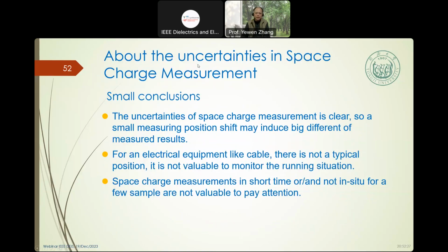So, a small conclusion: the uncertainties of the space charge measurement are clear. A small measurement position shift may induce a big difference in the measurement. You move a little, maybe a big difference. For electrical equipment like the cable, they are not at a typical position, so it's not viable to monitor running insulation. Space charge measurement in a short time, or on just a few samples, is not viable to pay attention to and analyze.